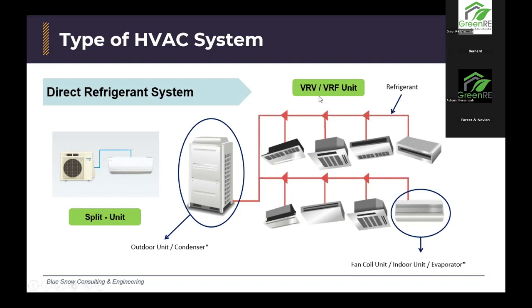But for the VRV, the outdoor unit is all bigger. And for the indoor unit, we can connect to multiple and a lot of types of indoor unit. We have wall mounted, cassette, FCU, fan coil unit, or what we also know as evaporator unit. So one of these outdoor units can supply multiple indoor units. That one is for VRV, and the split unit is one outdoor unit, one indoor unit. So this one is for smaller capacity.